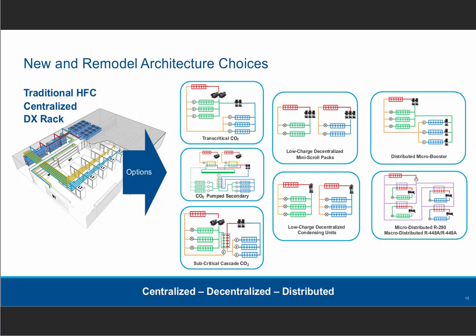I think we all realize that the majority of systems out there, the installed base of supermarket systems, are centralized HFC racks or HCFC racks that have been converted. And those are centralized. They have 2,000, 3,000, 4,000 pounds of refrigerant in them. They have thousands of feet of pipe, many, many joints. They've traditionally been the highest leak rate offenders. And that's why a lot of regulators are basically targeting large systems and looking at that first to try to reduce the direct emissions.